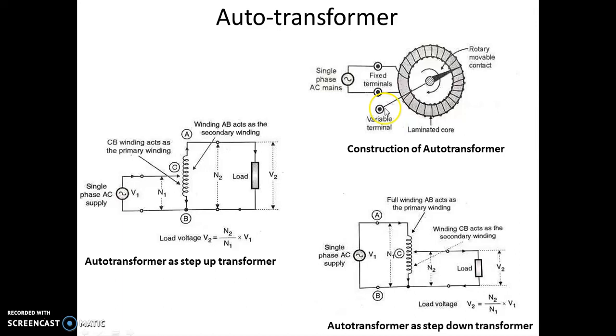Unlike a conventional transformer which has two windings — primary and secondary — this auto transformer has only a single winding which is wound around a laminated core. There is a movable contact which divides this single winding into two parts. The two fixed terminals act as the first winding, and the movable contact creates a second part which acts as the second winding.